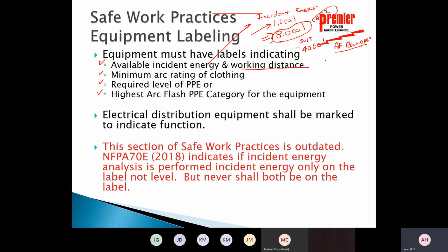Then they have the working distance. There are two boundaries there. One is restricted, one is limited. Restricted is the closest that you can get if you're a qualified individual. Like for 480 volts, that's going to be 1 foot for a qualified person. Limited approach is the closest you can get if you're unqualified. So again, for instance, 480 volts, that's going to be 3 foot 6 inches. So we're going to be given those boundaries.